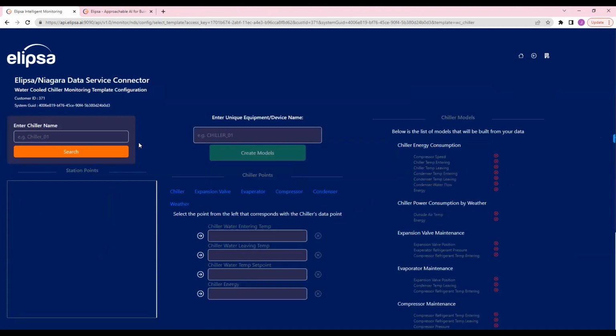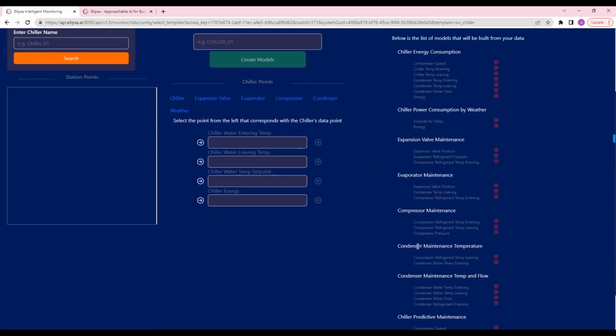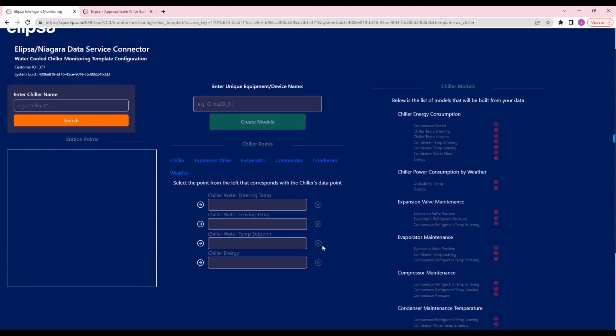Similar to the searching for points here, on our side in the middle, we have a variety of different data points that we need in order to create these machine learning models on the right. So we could automatically, if you map your data points and you have enough data points, create a chiller energy consumption model, a power-based-on-weather model, and individually monitor the expansion valve, evaporator, compressor, condenser, etc. That way, you're simply connecting your data for, say, this chiller, and it automatically goes through and creates all the models applicable to that device.